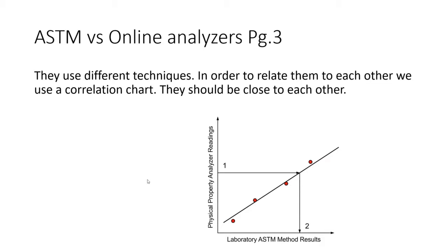If we overlay them, we see they're not exactly right, but we are characterizing the results — saying the online analyzer reads this number while the actual lab number will be this. It's a relative comparison. Once you're up and running with your analyzer online, you'll just run with the operating values with an understanding of what they represent compared to a lab sample. For example, if your analyzer says 400 ppm but you know the lab would read 390, that's fine as long as you understand it — that's the correlation process.